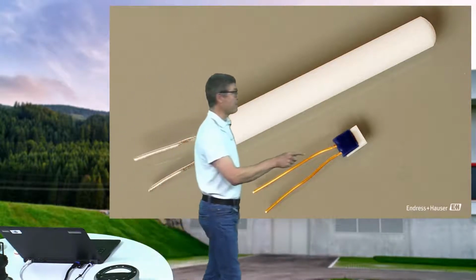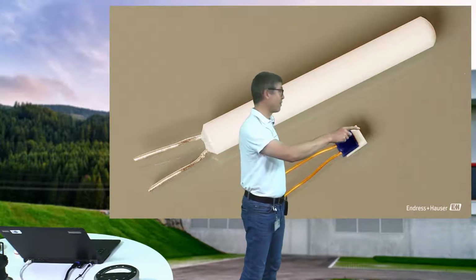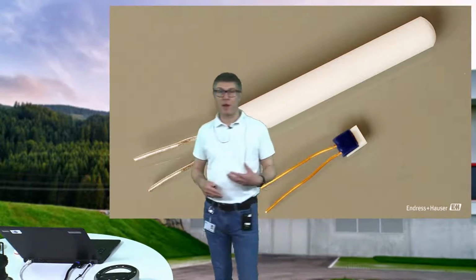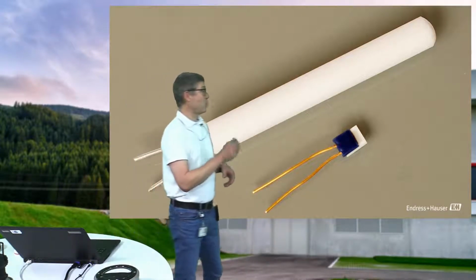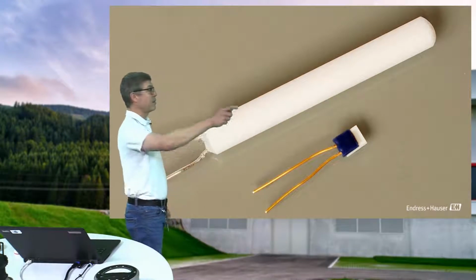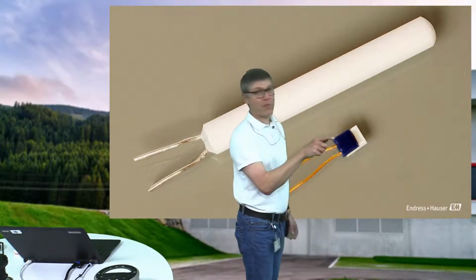And on the thin film thermometer, in the sensor itself the ceramic plate is white, and what you see here in a little gray is the thin film of platinum, which is going up and down until you reach a certain length, which reaches 100 ohm. We use, and all the colleagues use, mainly this thin film sensor. You can immediately see it's smaller, so it's easier to work with it, and the sensitivity is on this chip.